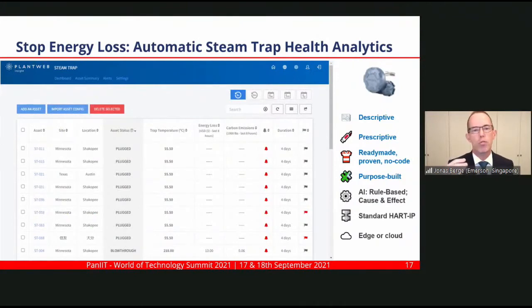Only the core process control is really automatic. For example, monitoring steam traps is very manual, through manual surveys usually done yearly. Since it's yearly, a steam trap can be blowing steam for 6 months to a year, costing you lots of money in loss of steam and increasing your carbon footprint. Another way it can fail is trapping condensate, which causes inefficiency and can lead to a whole host of other problems. So either way, this needs to be detected fast.